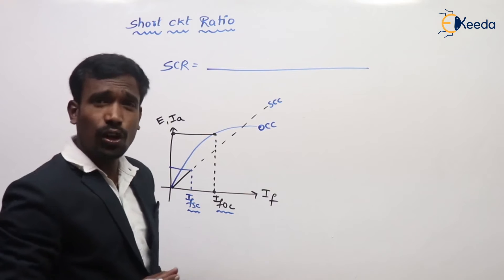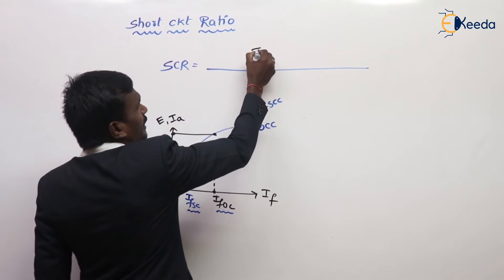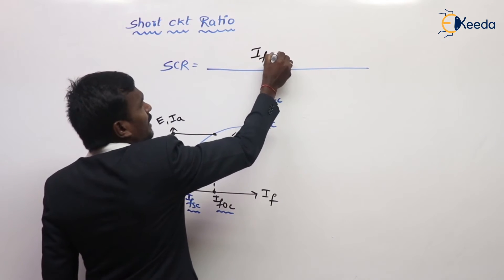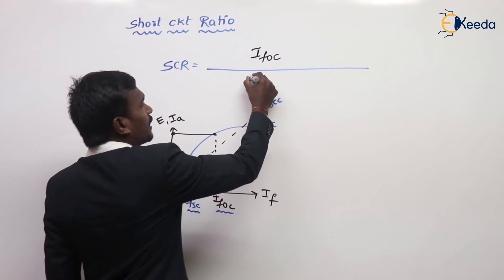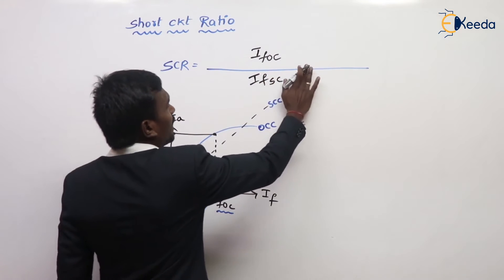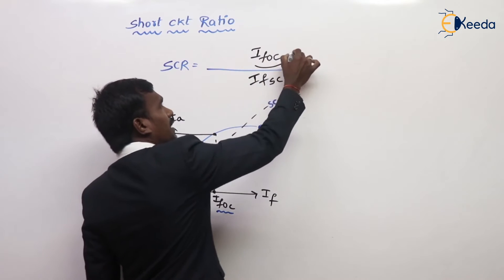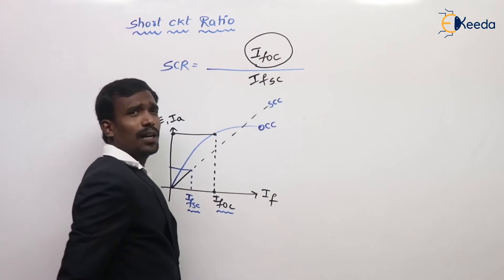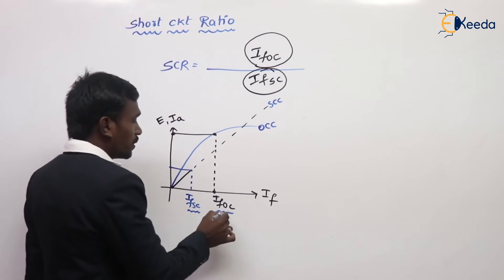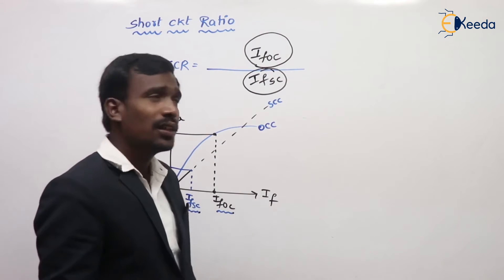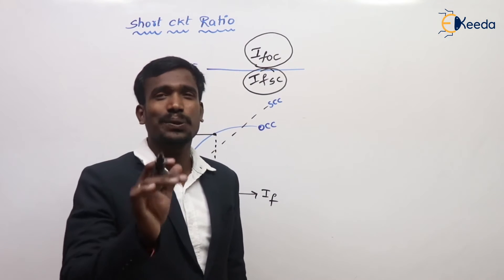So what is short-circuit ratio? Short-circuit ratio is the field current required to produce rated voltage on open-circuited armature, divided by the field current required to produce rated current on short-circuited armature — simply IFOC upon IFSC. This is our short-circuit ratio.